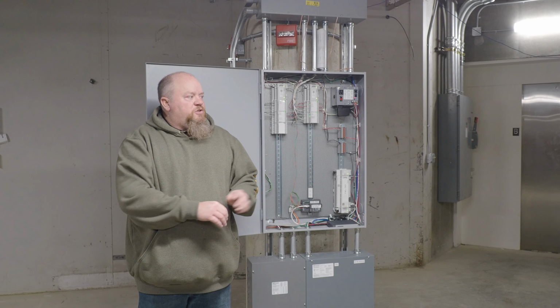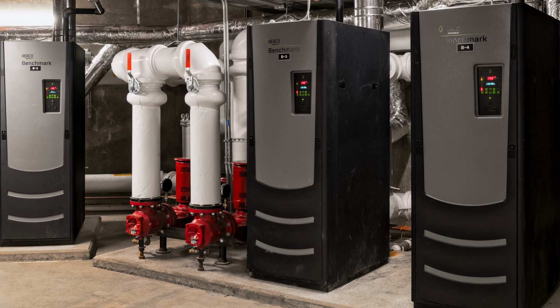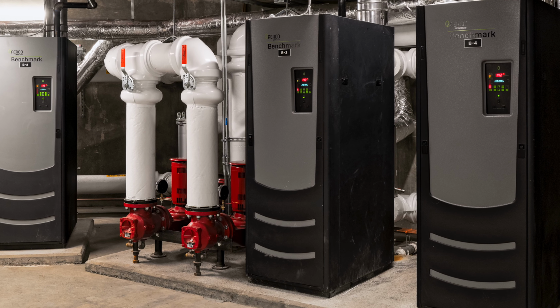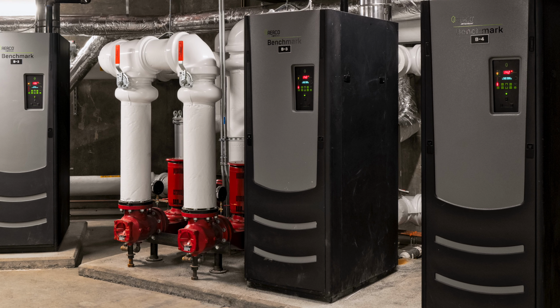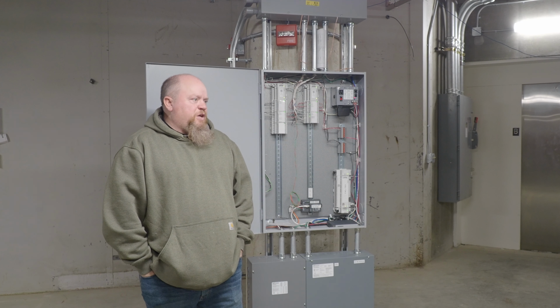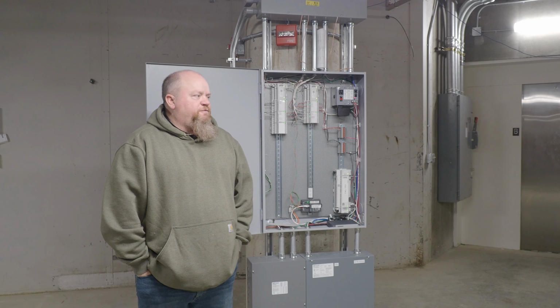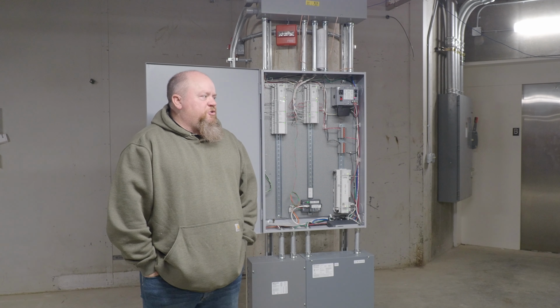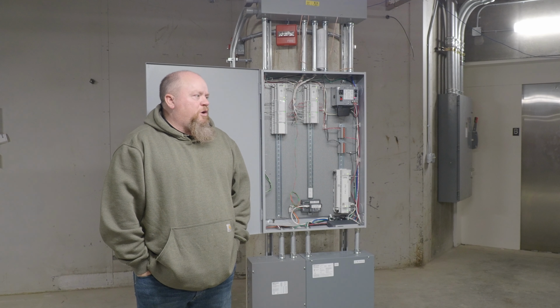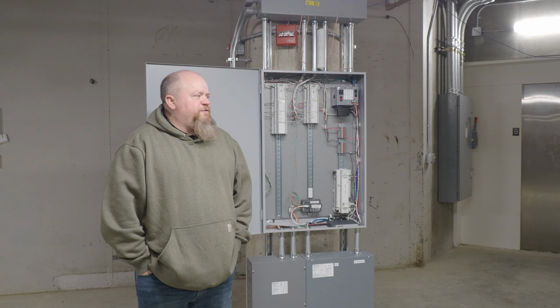As far as the boilers go, we need to try to maintain minimum flow for the boilers. We have a flow meter in line. There are issues with flow. When we go to turn on, if Aerco calls for 3 boilers, we can't pump enough water to flow. It needs 150 GPM per boiler, and the most we can get out is maybe 400. 3 would probably run, but with 4 you'll start getting some issues.